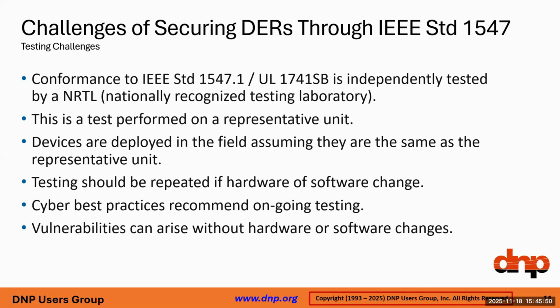Many current certification programs, like those in 1547.1 or UL 1741SB, are designed to verify functional compliance. They test a representative unit, with an assumption that all deployed devices will behave the same way, and we don't retest unless there's a major hardware or software change. But with cybersecurity, vulnerabilities can change and emerge even without such changes, so ongoing testing is important.